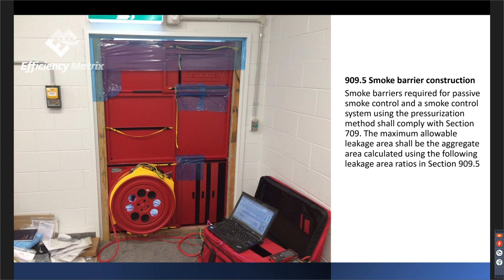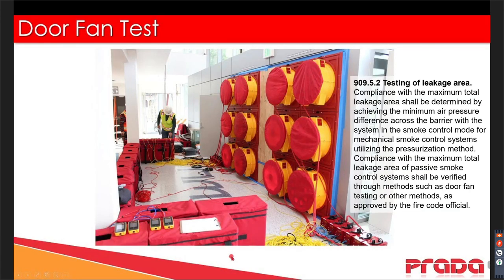So the point of 909.5, which talks about how the smoke barriers have to be constructed, lets you know that there is a maximum allowable area for leakage that is permitted. And there's actual calculations that can be done to show what that maximum allowable area is. As a rule, if the wall is being built sufficiently tight, testing of the leakage is probably not going to be required.